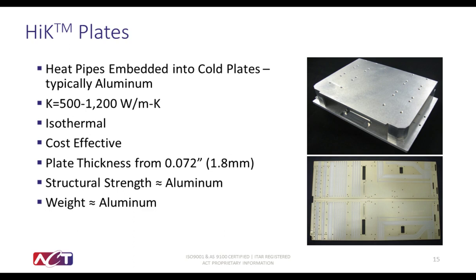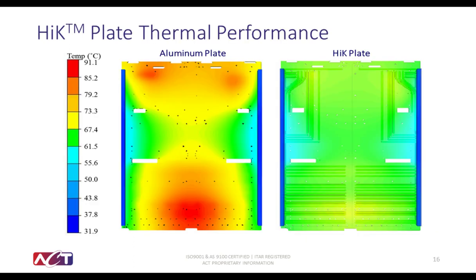As you can see in this example, where the customer has both an aluminum plate and a HiK plate in the same design, the maximum temperature on the aluminum plate is around 90 degrees C, whereas the maximum temperature on the HiK version of this plate is around 60 degrees C. This is achieved because the heat pipes are passively transporting that heat and spreading it throughout that plate, taking better advantage of all the mass available. Additionally, in this application, that plate was locked into a liquid-cooled chassis as denoted by the solid blue lines. Spreading that heat more evenly into this liquid rail reduces the flux and also increases the efficiency of the system.